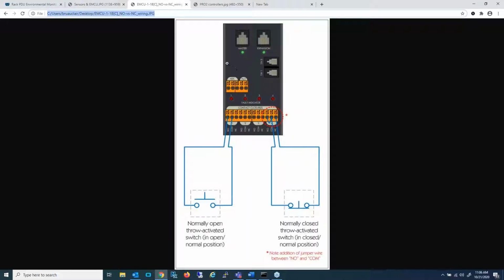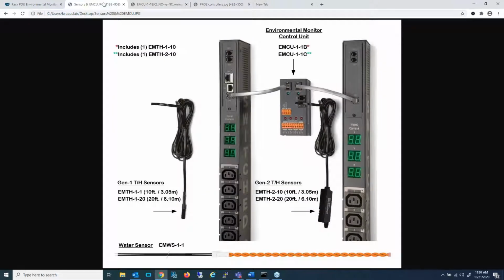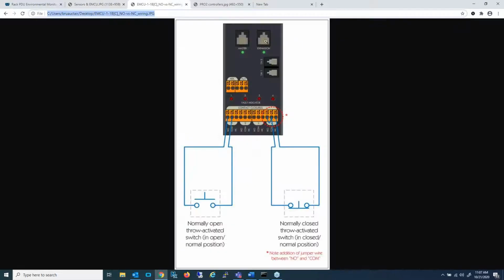So it is made to reside either just directly off the networked or parent PDU, in which case you connect it here. If there is a link or child PDU, it resides between the two, like we saw on this page, and the child PDU connects to this port. So we've got 4 contact closure monitoring points that can be normally open or normally closed, and a transition is what will create the alert.